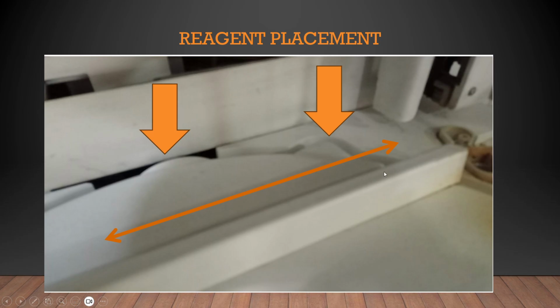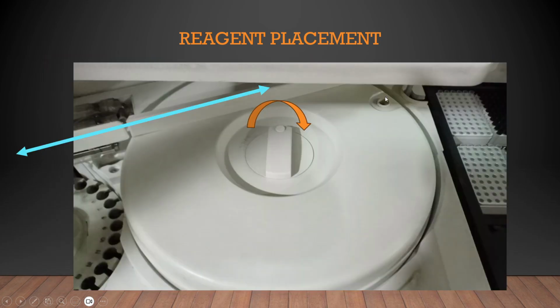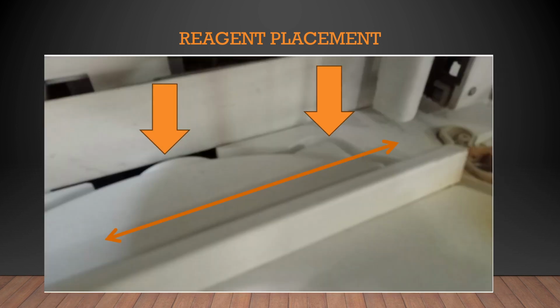Okay, if you don't fit the cap properly, what is going to happen: the mixer probe, which has to go in this single hole, and the reagent probe, which has to take from these small holes, will not go, they will get stuck and the instrument will not work. Okay, so for that reason you have to make sure about that part.